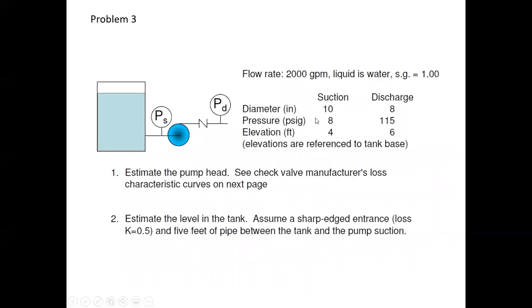Okay, so problem 3. We have, again, a suction tank, sharp-edged orifice. We have just a straight pipe into the suction gauge. Then we have the discharge on the pump. We have a check valve, and then we have the discharge gauge. So the flow rate here is 2,000 GPM. We got standard water, specific gravity 1. We've got suction and discharge diameters, suction 10, discharge 8. Pressure, suction 8, discharge 115, and elevation 4 and 6.